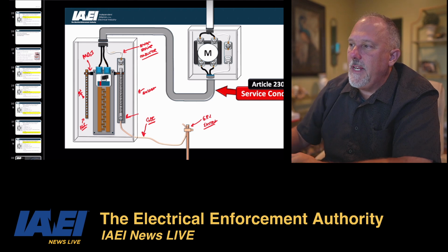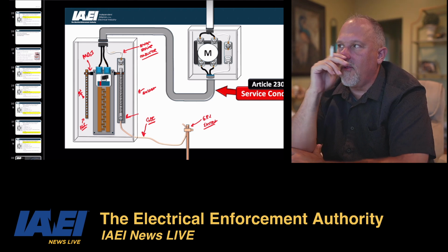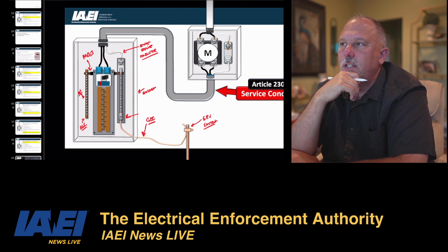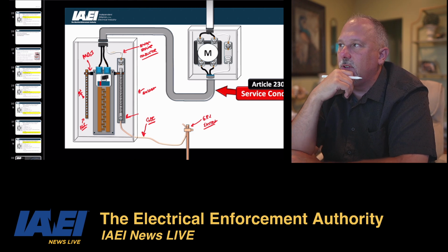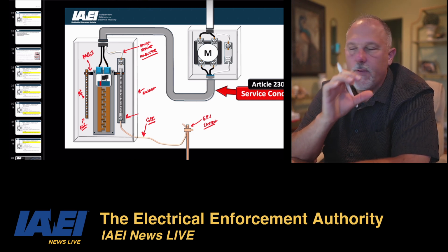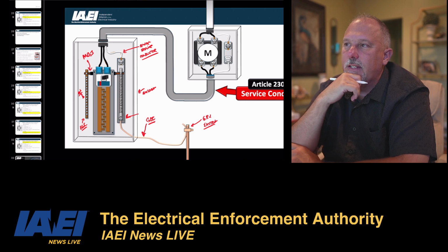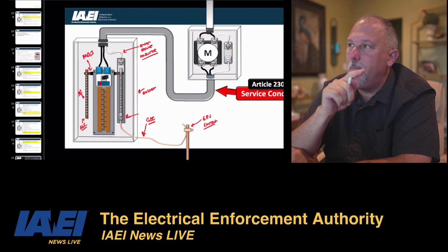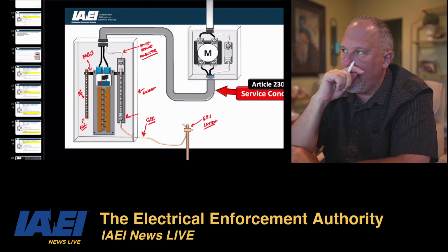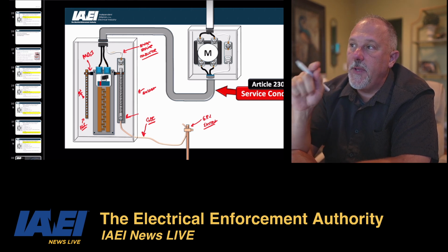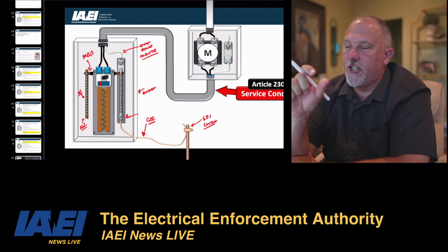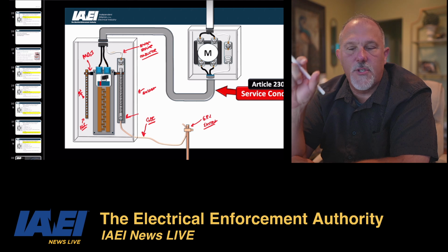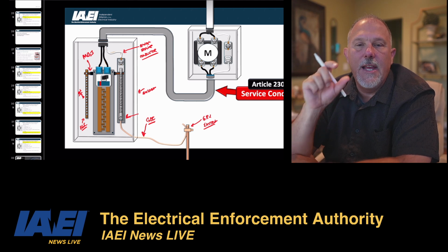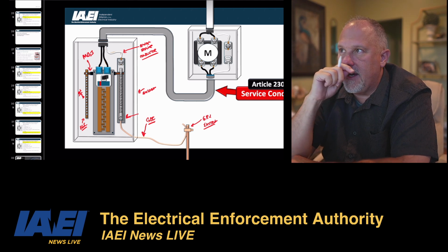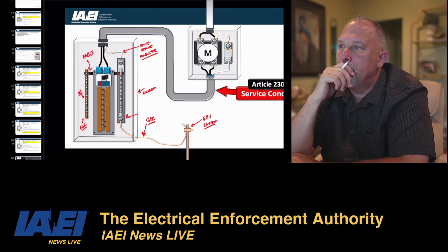Bonding jumpers meeting the requirements of this article shall be used around impaired connections, such as reducing washers or oversized concentric or eccentric knockouts. You want to make sure you have very good connections. Standard locknuts or bushings shall not be the only means for bonding required by this section, but shall be permitted to be installed to make a mechanical connection of the raceway. So you can't use some of these connections as bonding for the service.